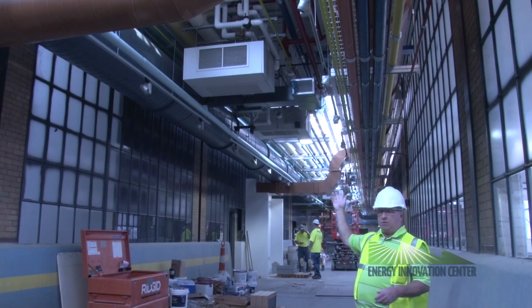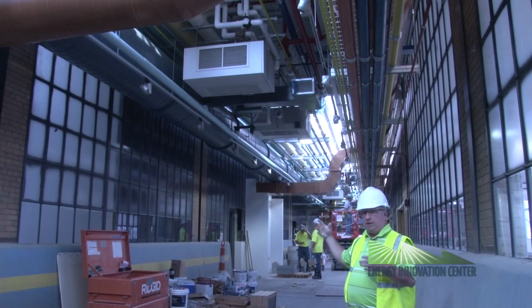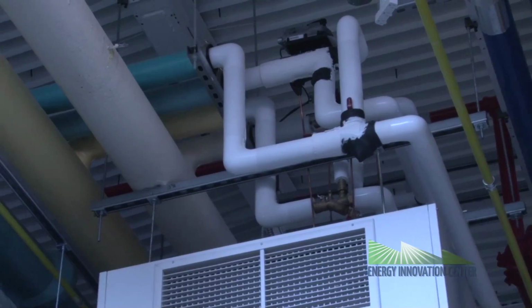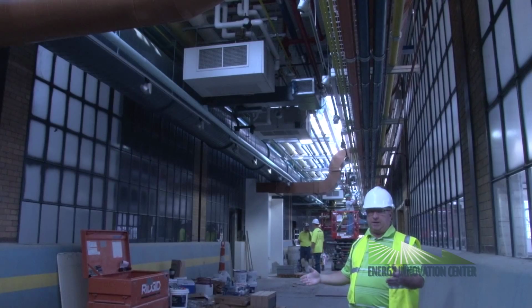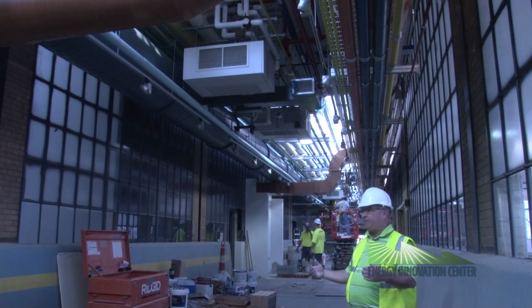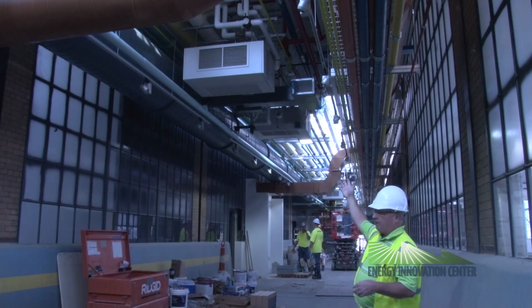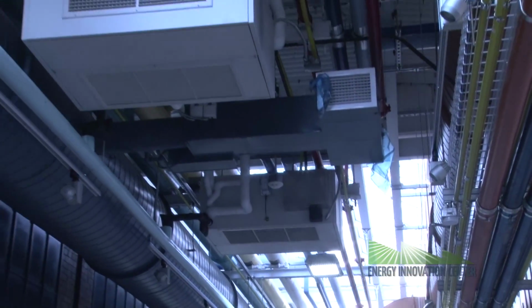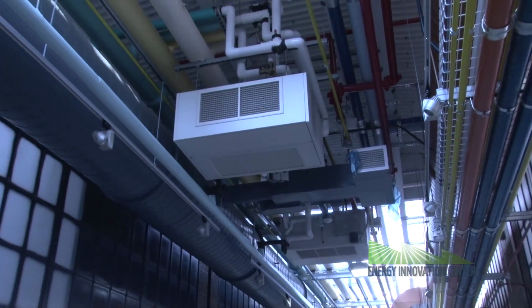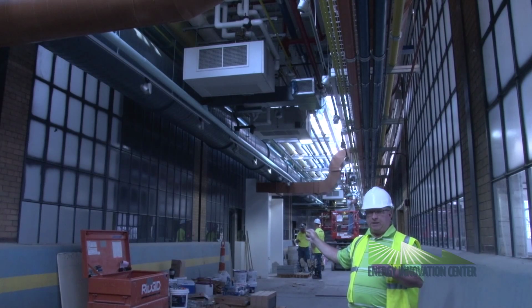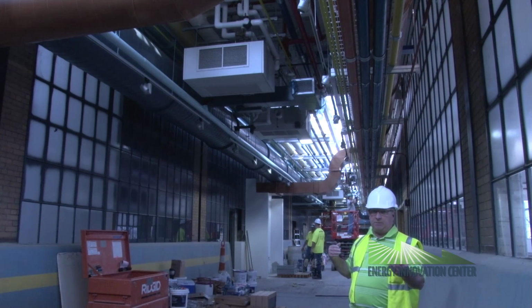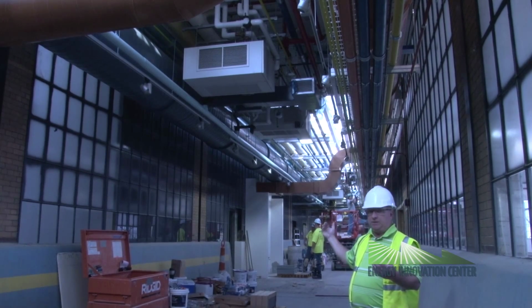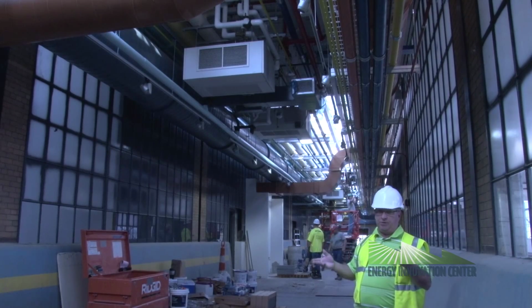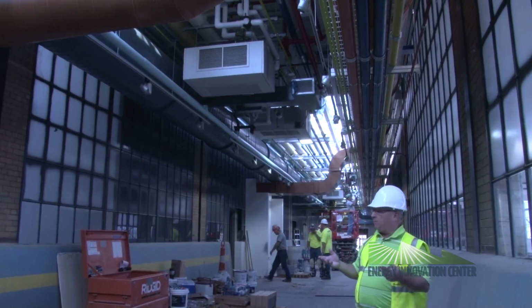As you have seen, we've had multiple different configurations of technology here. These are horizontal fan coil units that we have in the corridor space. The blue duct coming out is our fresh air from outside. We mentioned before the dedicated outside air systems. It comes into the building, and the fan coil units trim, heat and cool that air. The air that's coming in is pre-treated so that the humidity is at a stable level and the air coming in is at a stable temperature. The fan coil units will do very little work in order to maintain that.